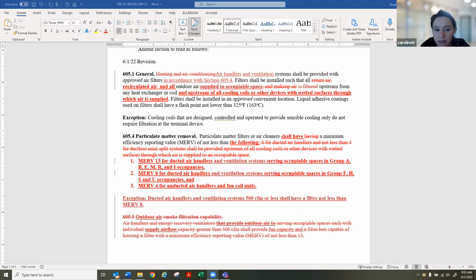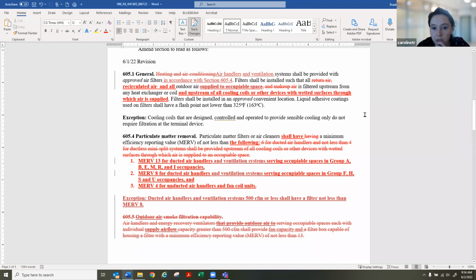So I guess looking back at 605.1, the first sentence seems straightforward. The second sentence, Krista, do we need to unstrike out the "is filtered"? So filter shall be installed such that all recirculated air and all outdoor air is filtered. Yeah, that guy. Upstream from any heat exchanger or coil and upstream of all cooling coils or other devices with wetted surfaces through which air is supplied. Eric.